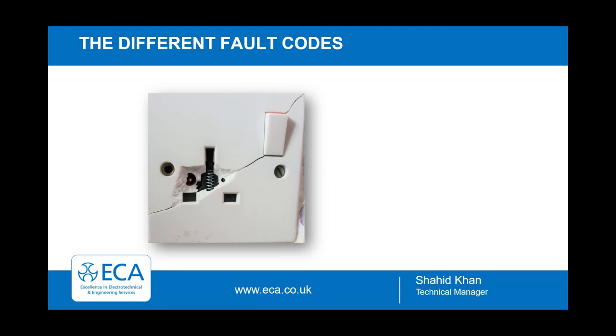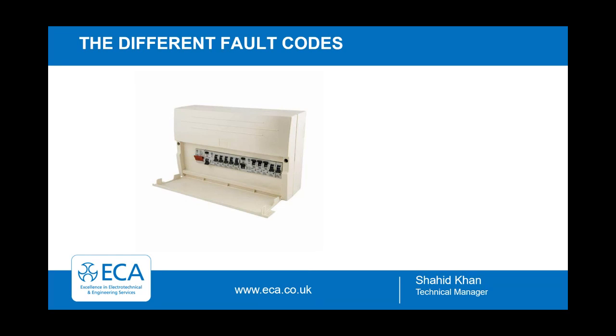Is there something missing there, Shahid? There is. So I've gone with a C1 for the obvious defect in terms of the failure of basic protection. But there's also a screw missing. I know a lot of people have said that I've got a screw loose, but this thing definitely has. On the left hand side, you can see that clearly it's not secured correctly. Hence why I'd also give it a C3. In terms of regulation numbers for the C1, it's the IP requirements again, so 416.2.1, and for the C3, it's good workmanship, so it's 134.1.1 in that case. Obviously, Mike and I couldn't see that missing screw because we don't have our glasses on.